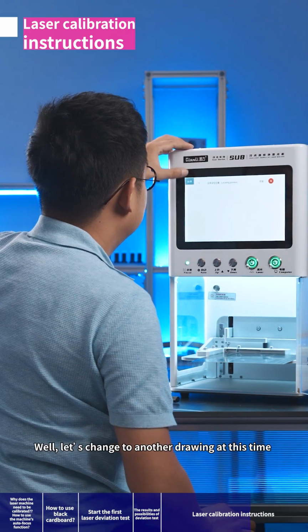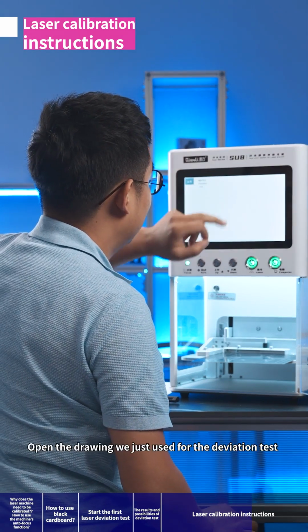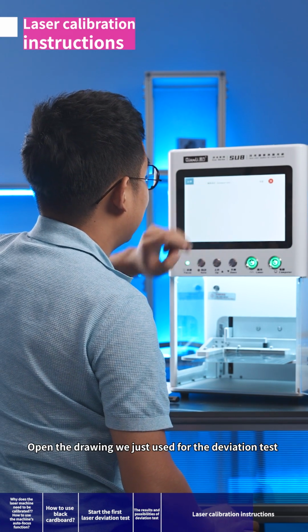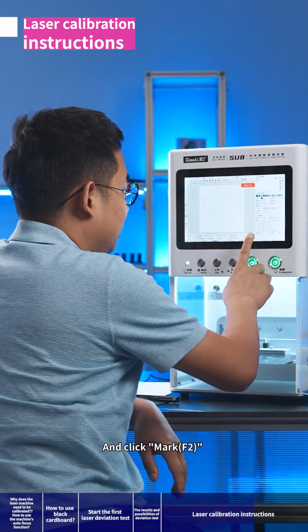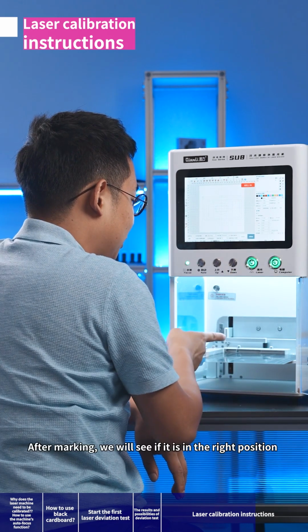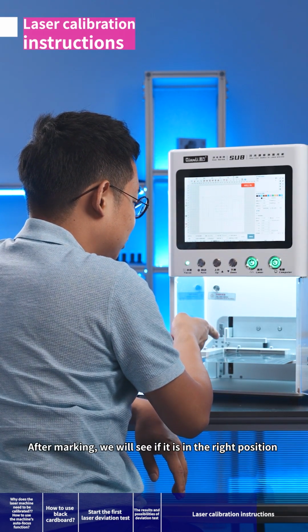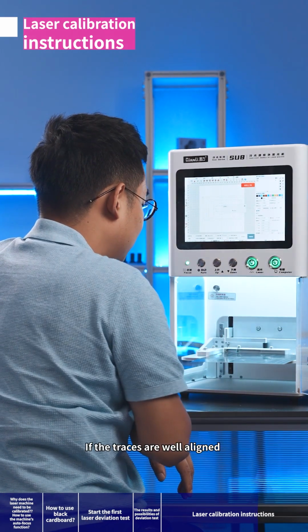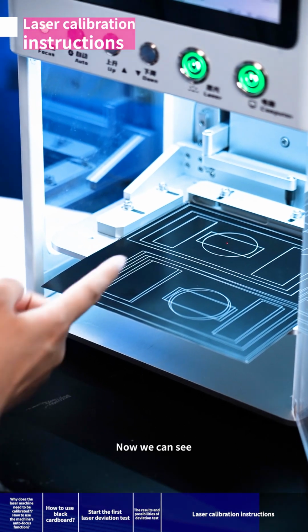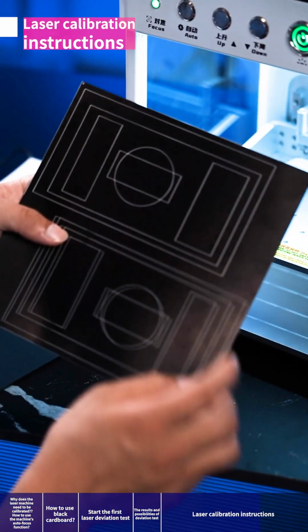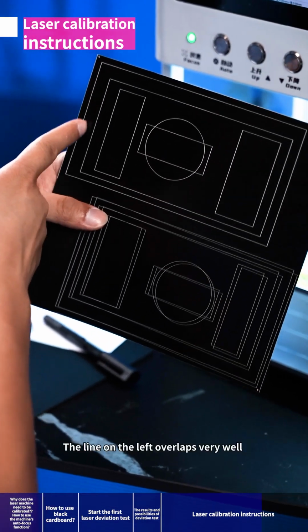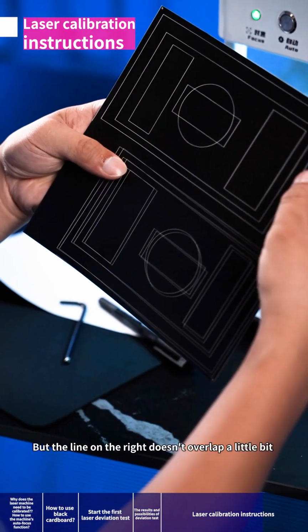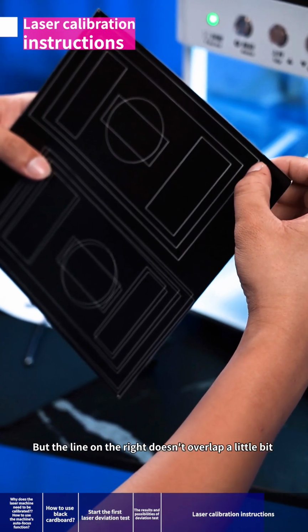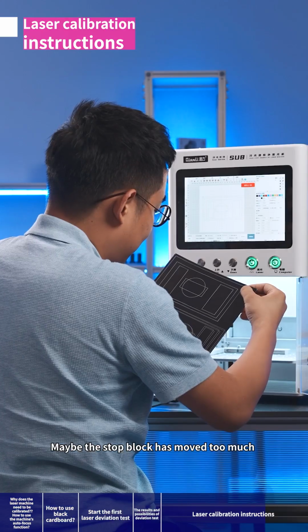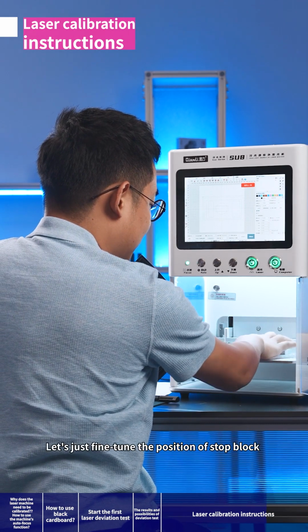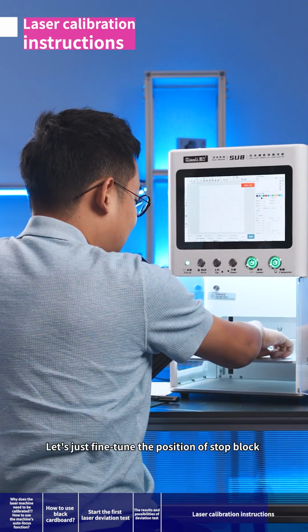After aligning, make sure the cardboard is flat. Well, let's change to another drawing at this time. Open the drawing we just used for the deviation test. And click mark F2. After marking, we will see if it is in the right position, if the traces are well aligned. Now we can see. The line on the left overlaps very well. But the line on the right doesn't overlap a little bit. Maybe the stop block has moved too much. Let's just fine-tune the position of the stop block.